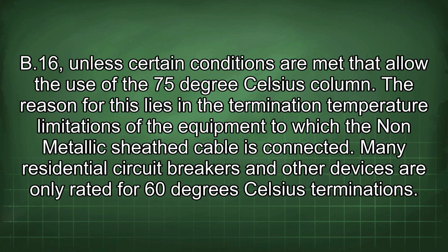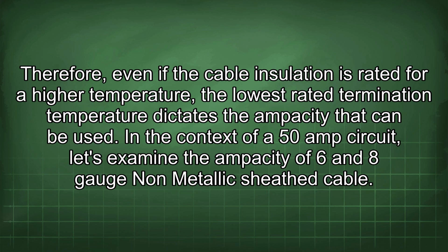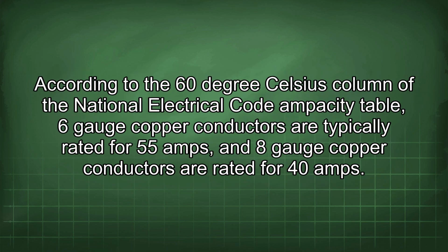The reason for this lies in the termination temperature limitations of the equipment to which the non-metallic sheath cable is connected. Many residential circuit breakers and other devices are only rated for 60°C terminations. Therefore, even if the cable insulation is rated for a higher temperature, the lowest rated termination temperature dictates the ampacity that can be used. In the context of a 50-amp circuit, let's examine the ampacity of 6 and 8 gauge non-metallic sheathed cable. According to the 60°C column of the National Electrical Code ampacity table, 6-gauge copper conductors are typically rated for 55 amps, and 8-gauge copper conductors are rated for 40 amps.